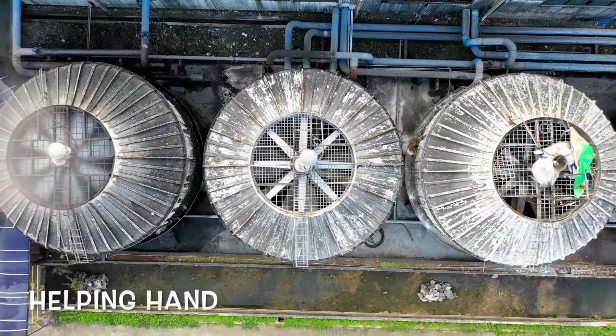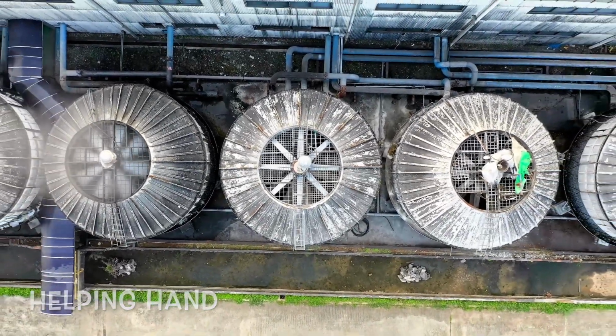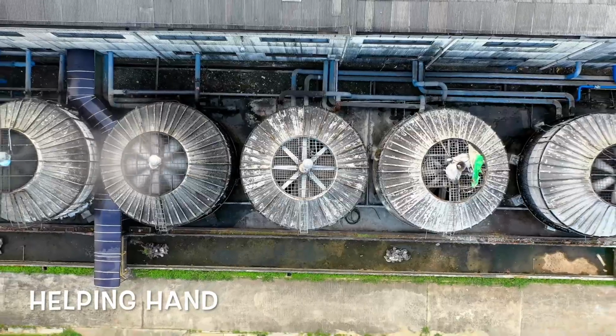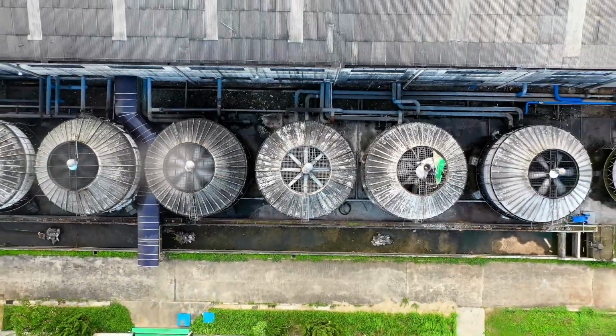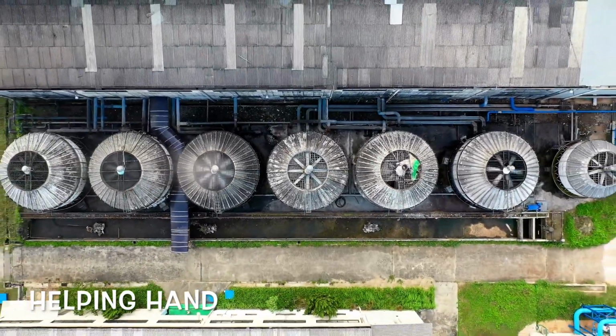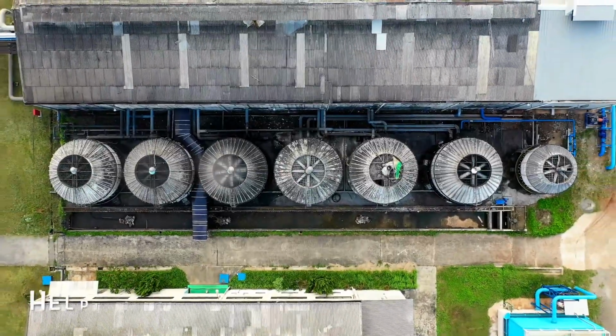Inspect the wiring. Check the wiring connections to ensure they are secure and not damaged. Loose or faulty wiring can prevent the fan from receiving power.